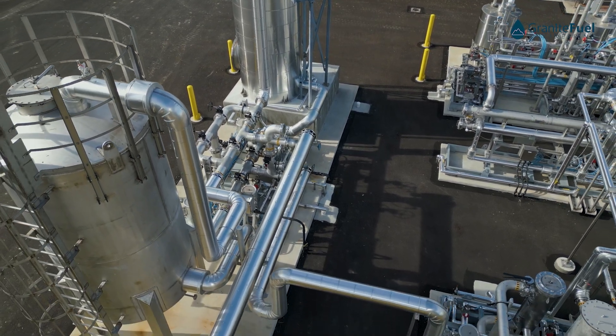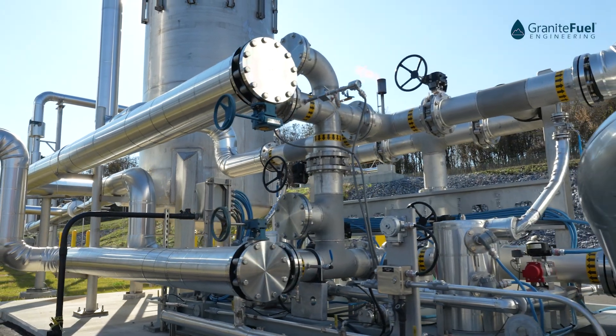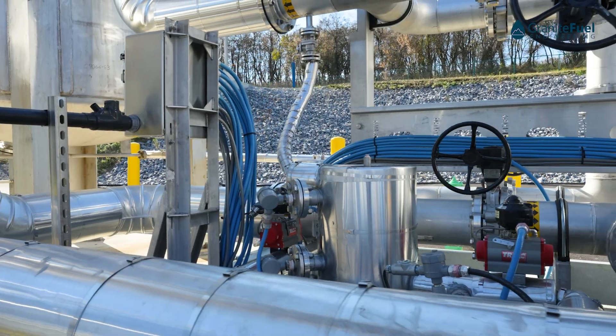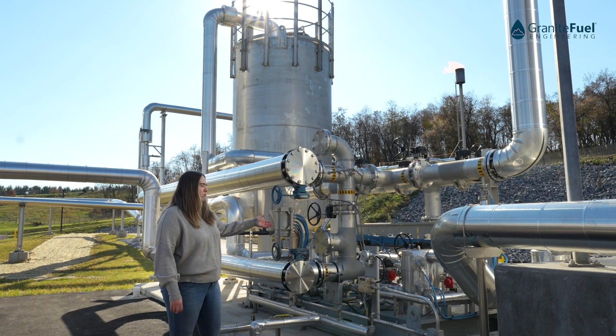The gas coming into the H2S removal system is relatively saturated, so on our lead-lag and parallel valve skids we have condensate accumulators that will collect the condensate at the bottom of the tanks and remove it as needed.